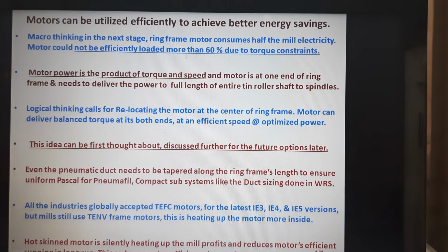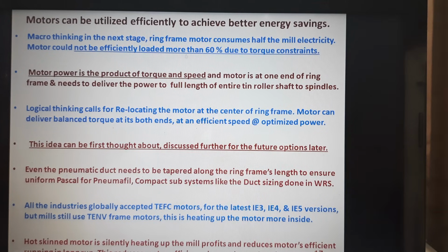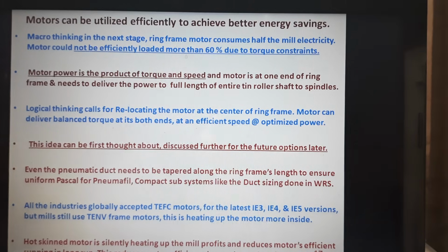Coming to the motors, throughout the industry segments, all the other segments have gone for TEFC motors, the IE3, IE4 and IE5 versions, but our textile mills are still using these TENV motors, non-ventilated motors, where the motors are getting heated up gradually, and sometimes accelerated heating up is known, and accelerated aging of the motor also happens. So definitely a hot-skinned motor is a silent loss to the mill. Let us see that the motor's skin is not hot, it is only warm, and let us try to dissipate the heat from the motor to the surroundings and keep the health of the motor sustainable for longer years as such.